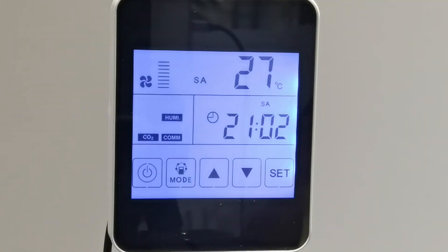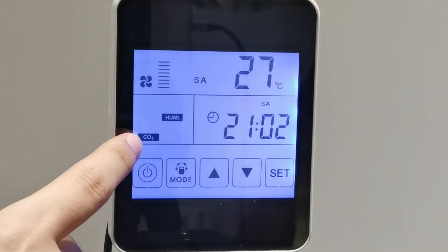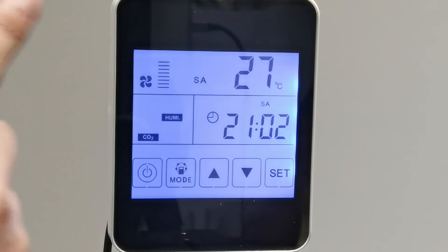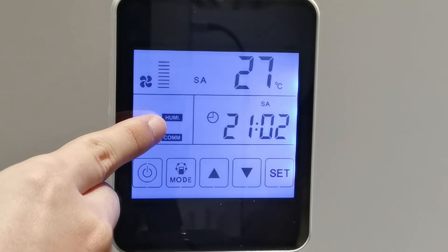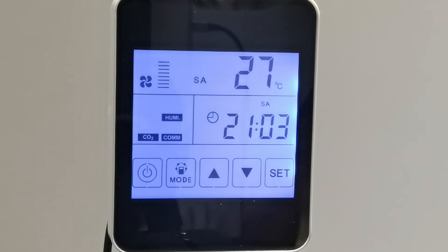The CO2 symbol appears on the panel. If the ERV is connected to a CO2 sensor, the logic is: when the CO2 concentration is higher than the setting value, the ERV runs at highest speed until the concentration drops below the setting value. There is also a humidity symbol that appears when a humidity sensor is connected. When humidity is higher than the setting value, the ERV will run at highest speed automatically until humidity drops below the setting value.